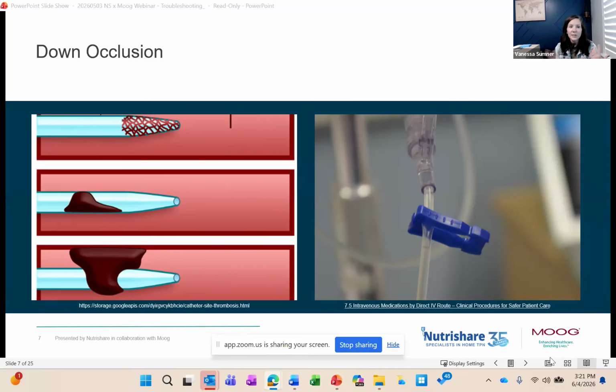But pumps, just like the air in line setting, also have a downstream occlusion alarm setting. So for example, if you're infusing a viscous fluid like TPN, it can be a little bit thicker than just normal saline. It may be more likely to have alarms, and you would want a pressure setting that will allow more pressure to build up before that alarm is triggered. If your setting on the pump is too sensitive, you're going to get alarms much more often while you're infusing. If the pump setting is less sensitive, it will allow for more pressure to build up in the tubing before that pump's occlusion alarm is triggered.